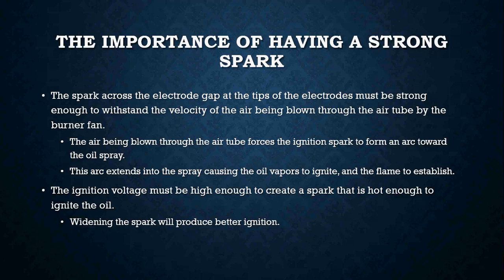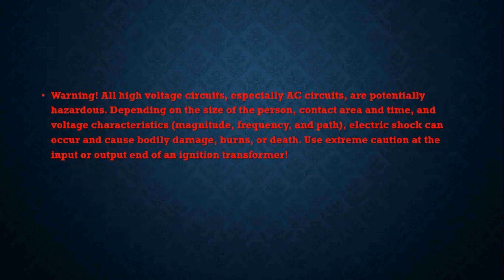So widening the spark sometimes will produce better ignition. It all depends on the burner. It depends on the type of ignition system that you're dealing with. But always remember one thing: you're dealing with high voltage. You're dealing with 10,000 to 20,000 volts of electricity. So you have to be very, very careful.